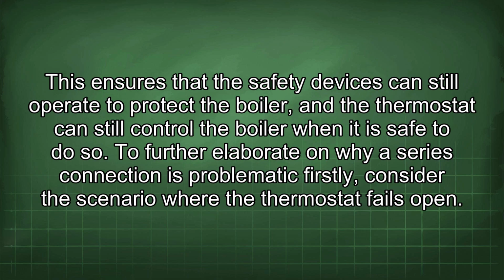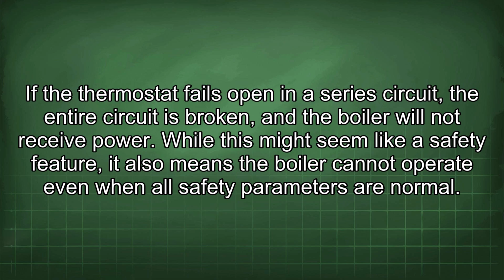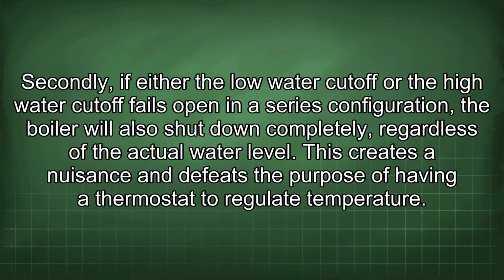To further elaborate on why a series connection is problematic, firstly consider the scenario where the thermostat fails open. If the thermostat fails open in a series circuit, the entire circuit is broken and the boiler will not receive power. While this might seem like a safety feature, it also means the boiler cannot operate even when all safety parameters are normal. Secondly, if either the low water cutoff or the high water cutoff fails open in a series configuration, the boiler will also shut down completely regardless of the actual water level. This creates a nuisance and defeats the purpose of having a thermostat to regulate temperature.